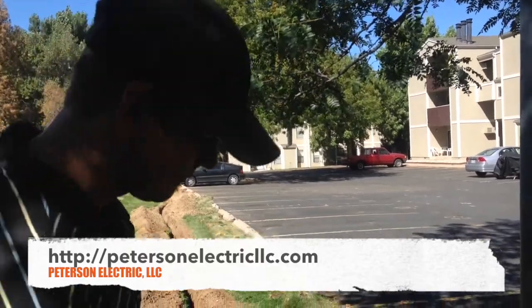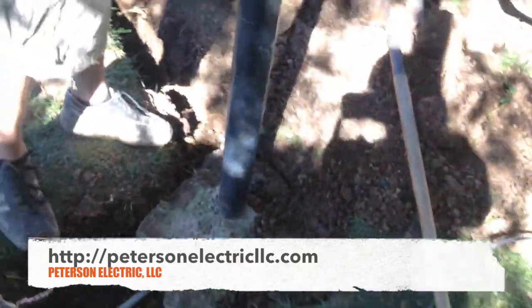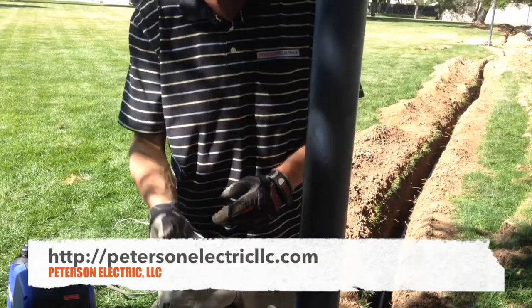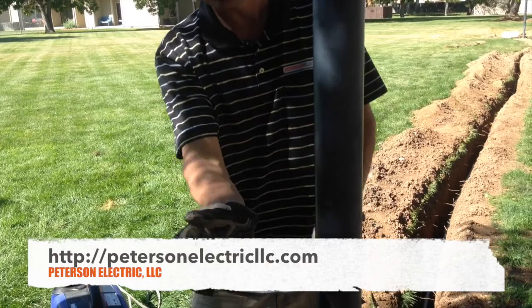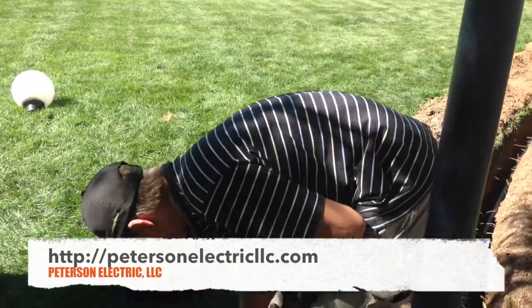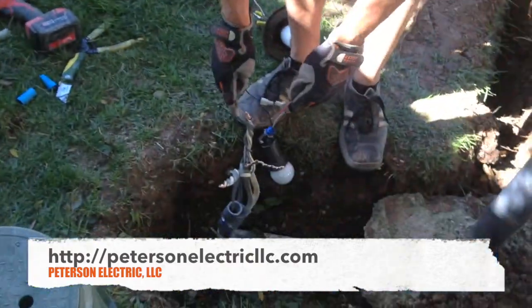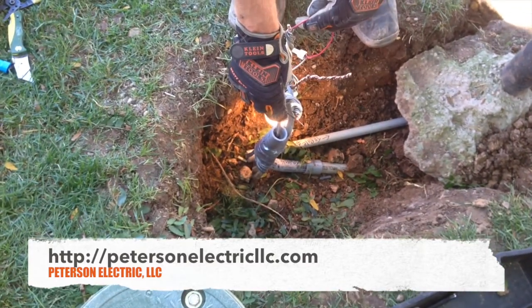If you're standing here with shoes you're never going to know if you're getting bit that hard. But if you take off one shoe and your sock and put your heel down, staying on the same side of your body, you might be able to feel a tingle. This is 120 volts — I know that because if it were 277 I'd blow this bulb very quickly. I'm testing my power as I finally corrected this.